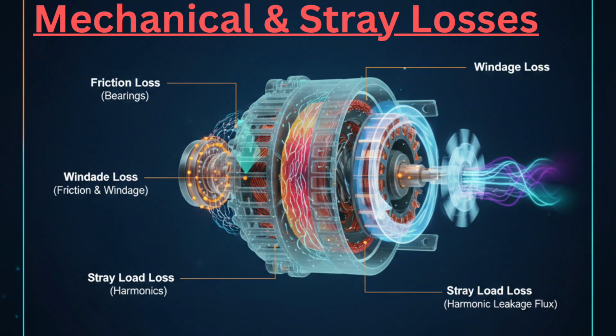Stray load losses are illustrated by irregular magnetic flux paths and harmonic waves. They are caused by leakage flux, non-uniform current distribution, and slot harmonics in the stator. Although smaller compared to copper losses, they still contribute to heating. Abnormally high mechanical losses may signal lubrication failure, misalignment, or blocked ventilation ducts, issues that marine engineers must rectify immediately to maintain safe generator operation.